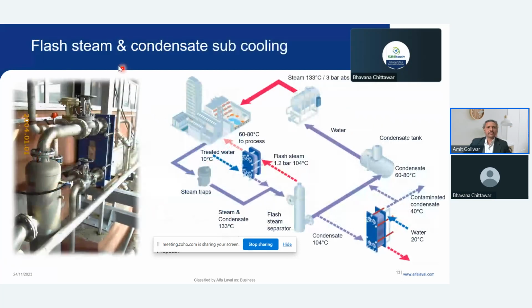Next is flash steam and condensate subcooling. In a typical process plant, the boiler generates steam. Steam goes into the process plant. The process plant generates water, condensate, and the steam trap separates it. It comes to either a flash vessel or it goes straight away to the boiler under the back pressure. This is a very good system because you are utilizing heat, you are utilizing condensate, you are utilizing water.